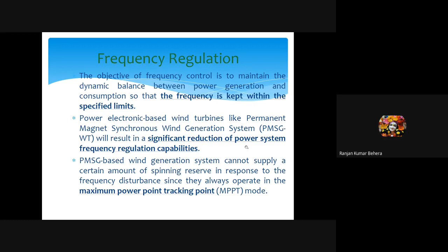And a PMSG-based wind generator system cannot supply a certain amount of spinning reserve in response to frequency disturbance, since they always operate in maximum MPPT mode. So in a conventional generating system you have a spinning reserve, whereas here you do not have that. So how do you operate this?